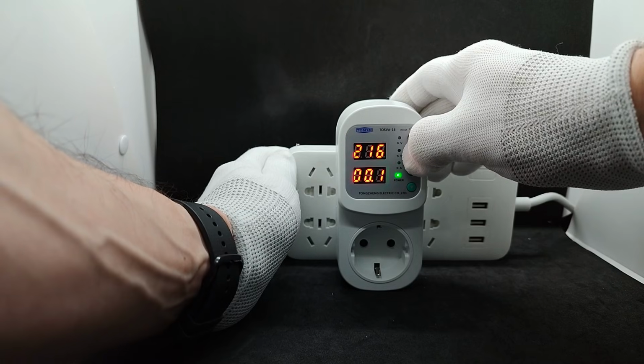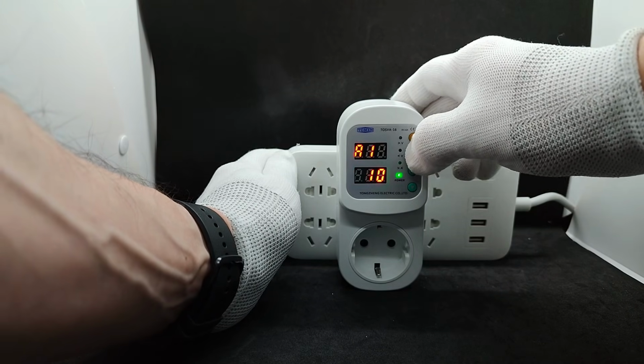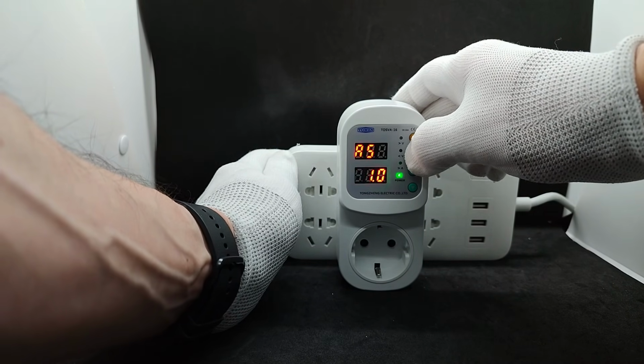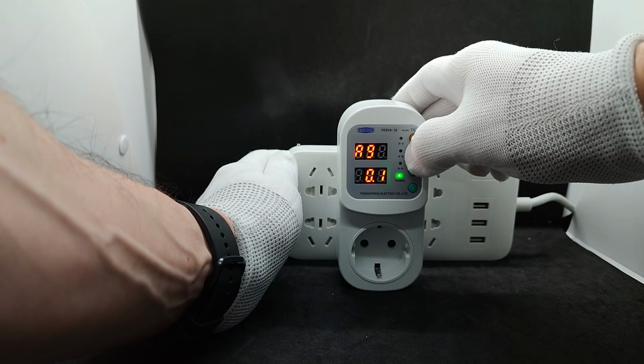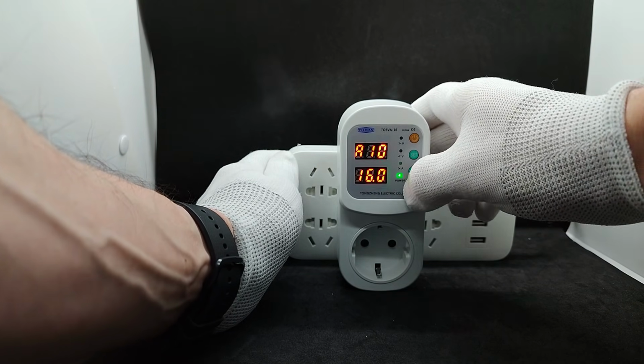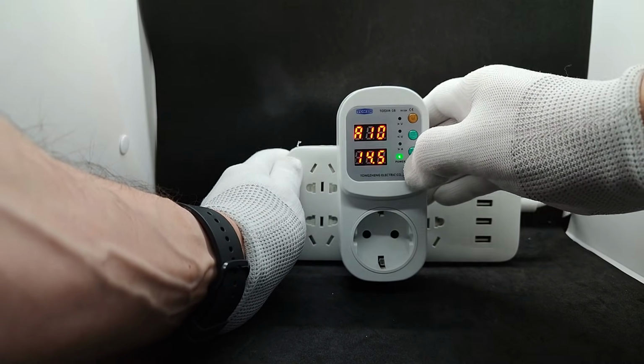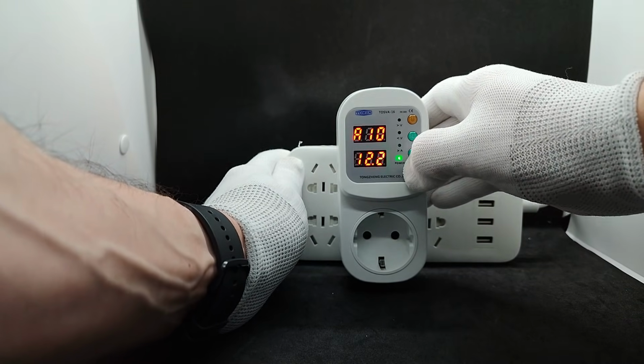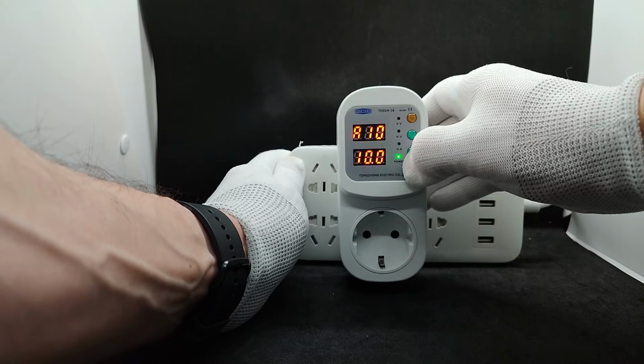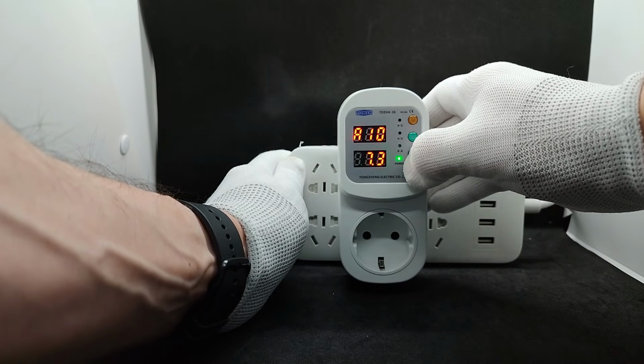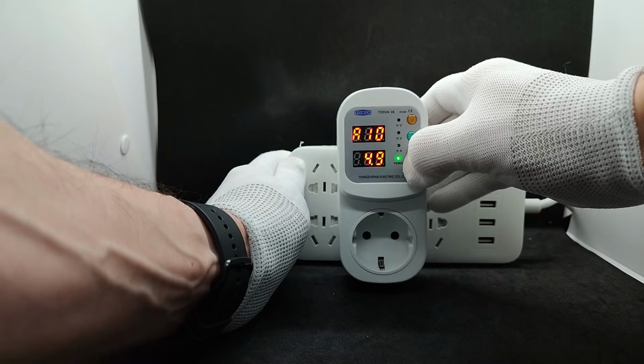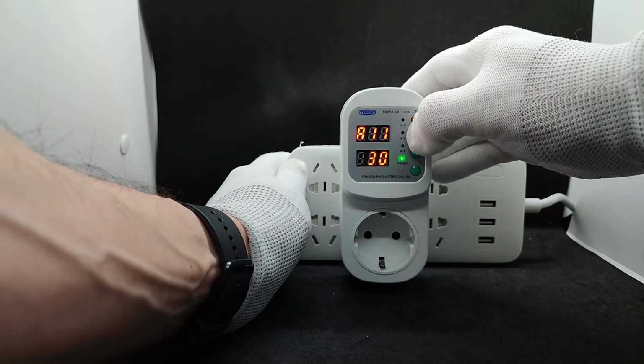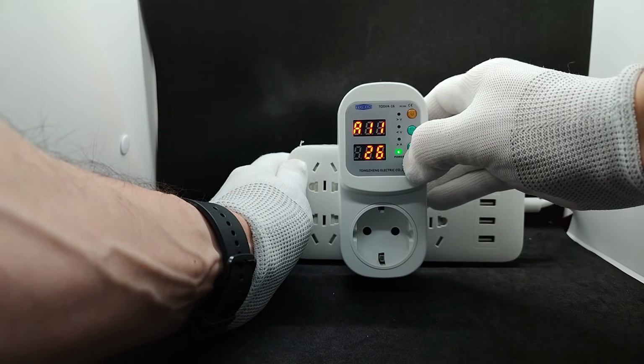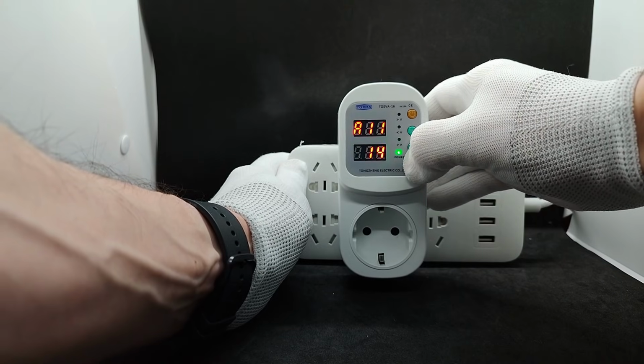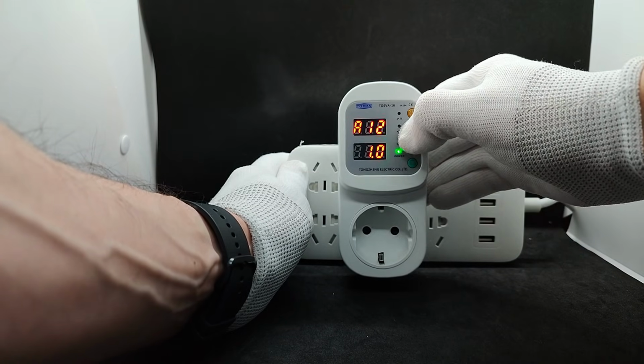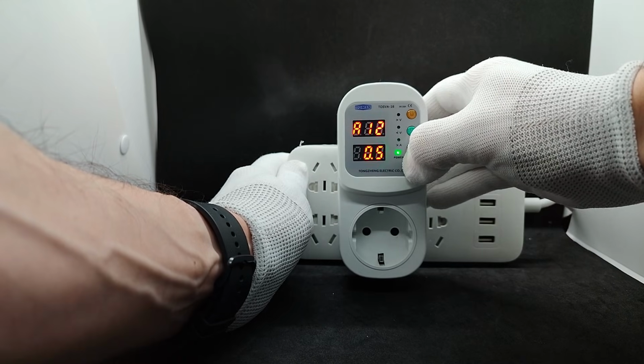It is difficult for me to reproduce an increase in voltage, so we will test overcurrent protection. We need item A10. By default, it is set to 16 amps. I remind you that for fast and smooth value changes, you can simply hold the arrow button. In this case, it is just not very convenient for me to do so. I set the value to 4 amps. Item A11 is the delay before rechecking. I set 10 seconds. Item A12 is the delay before shutdown. I set 0.1 seconds.